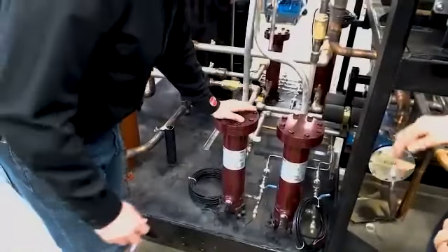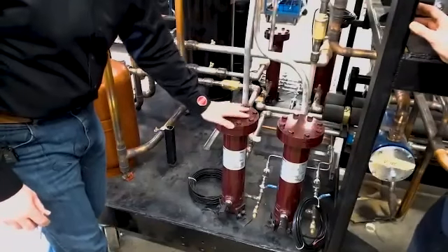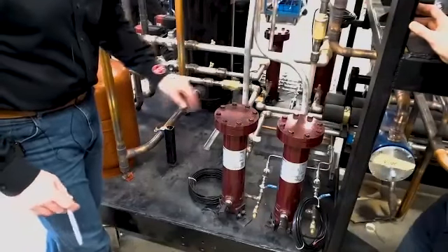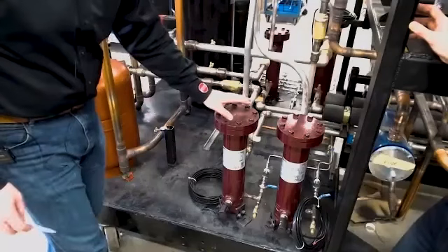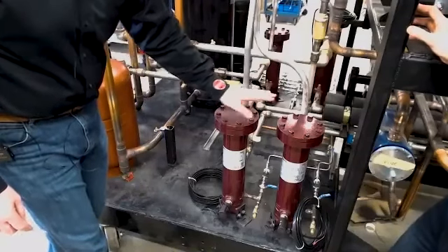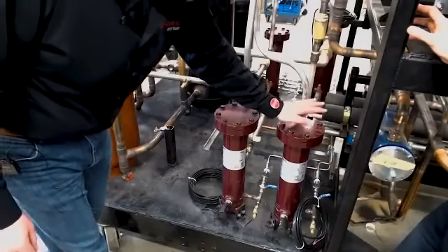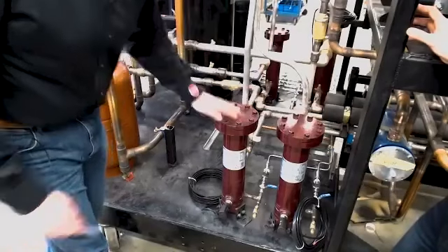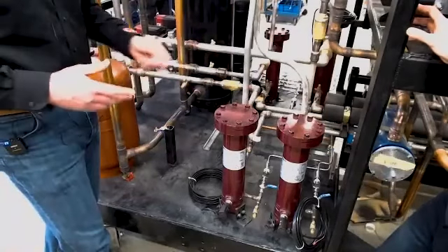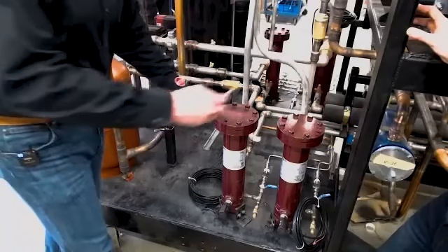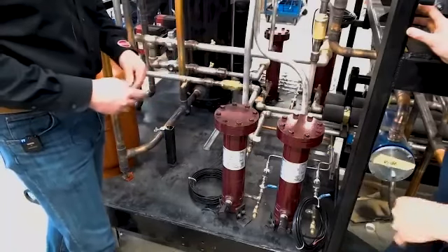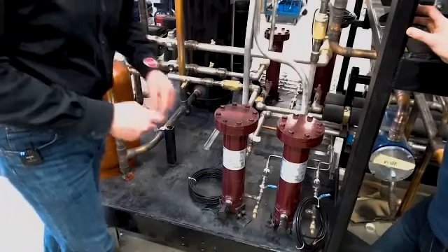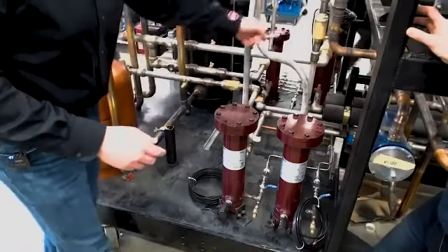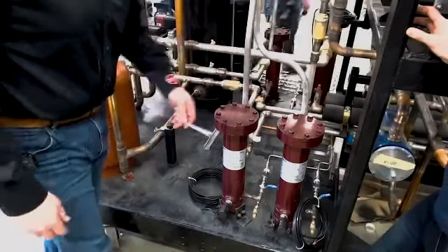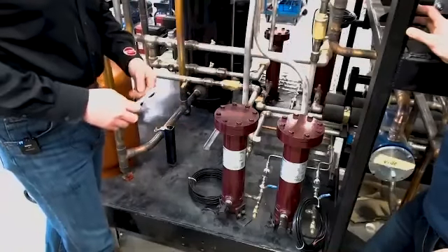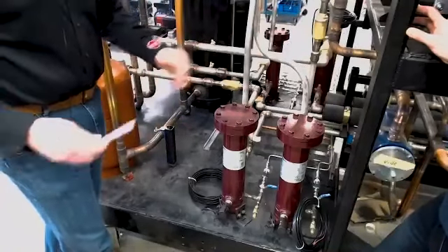So a recipe that we associate well with is having the ability never to shut down the entire rack to change an oil filter. So regardless if it's supermarket, industrial, we will always have independent oil separator groups. And it's just appropriately breaking up the compressors, because even in a supermarket application, we're not going to have all compressors running throughout winter. We're going to have some idle applications. So by breaking up the different oil separators, it allows us to do service. It allows us to pump out a suction group. It allows a great deal of flexibility in the overall design.